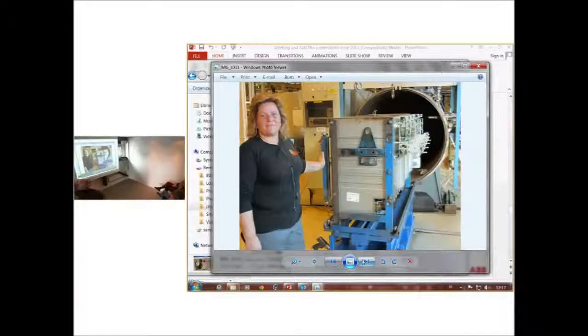You said over time there could be some diffusion, it could be a little bit lower over time. Yes, not because of leakage. So you see, this is the unit. Here you see this cooler ventil. What we do, we put the whole unit inside a huge chamber, and then we make a vacuum inside. The whole process takes about 20 minutes. When vacuum is achieved, we fill helium via this ventil, and then we pump up helium.